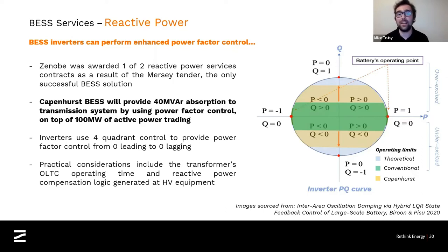So we can be injecting active power into the grid to meet demand as we see the frequency fall, or as we see a peak, at the same time as absorbing that reactive power. There are some additional practical considerations when designing for reactive power, and a really big one is that supergrid transformer I mentioned before. Capenhurst is connected at 275 kV because that has a much higher impact on the reactive power service. That also means we need that supergrid transformer, and transformers have big magnetic fields, which means they have a relatively big impact on reactive power. If we could have the next slide, please, Simon.